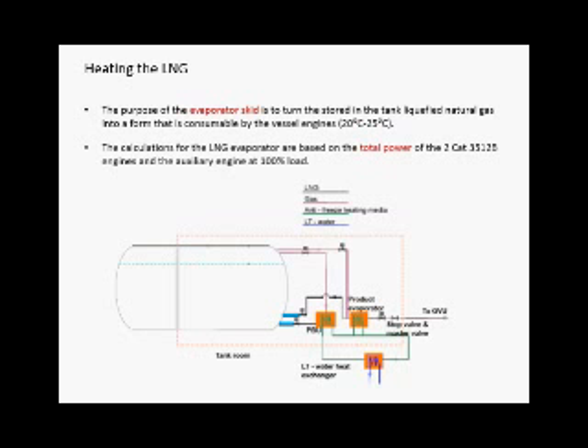Now there's another issue of how to design or select the size of each of these components, and of course the size of the piping system. This was the easy part. I need to remind you how the system operates, because as you can see, there is no pump installed. So how is the pressure of the boil-off gas kept at the specified level of 5 or 6 bars, and how is the pressure drop from the evaporator to the engine covered? This is a nice control problem, by the way.